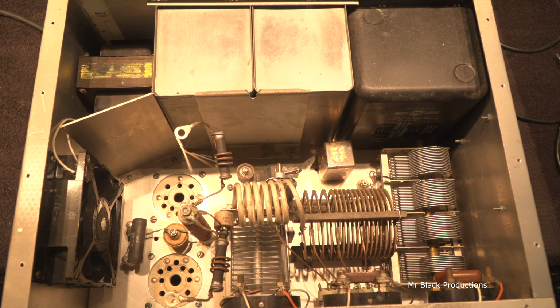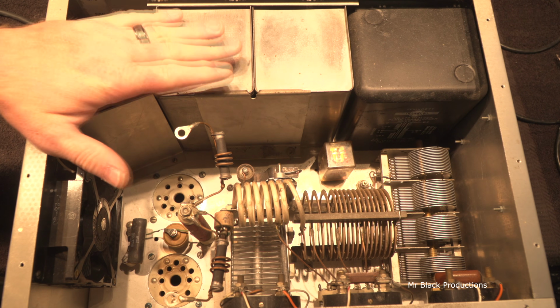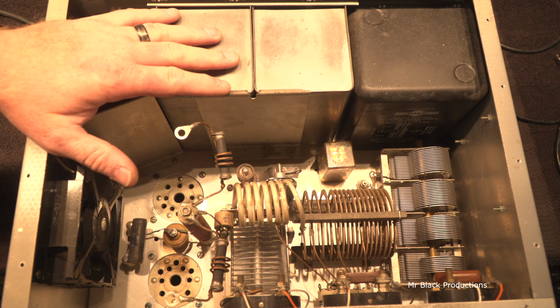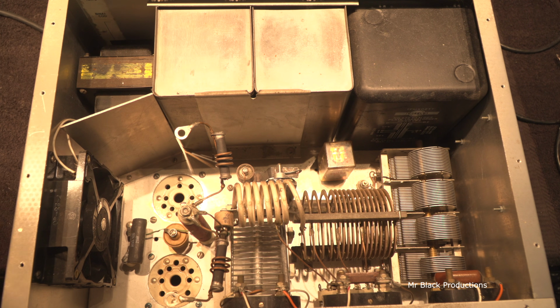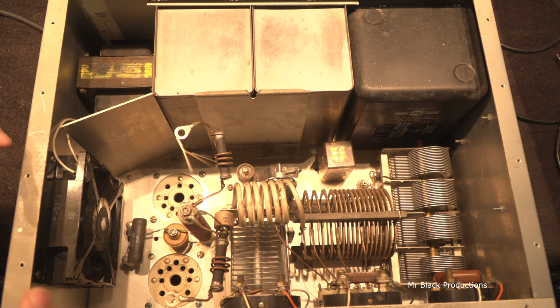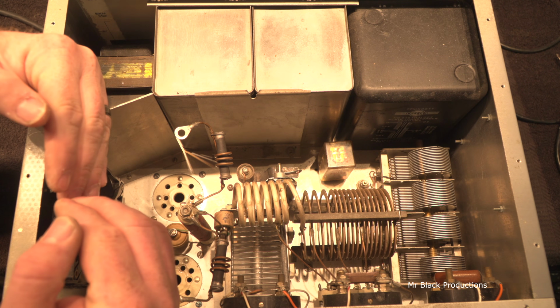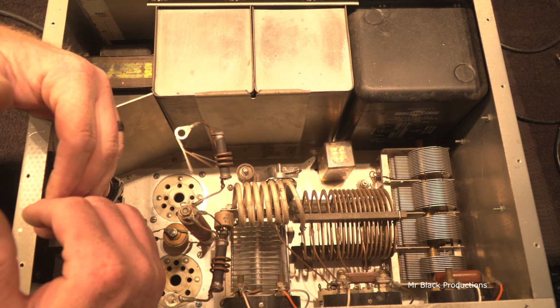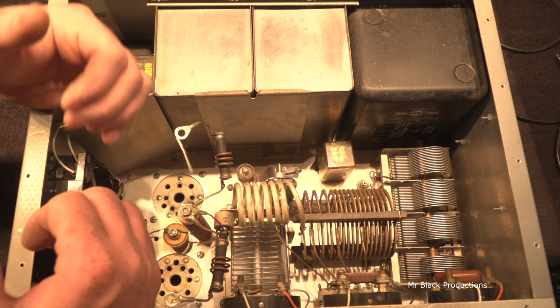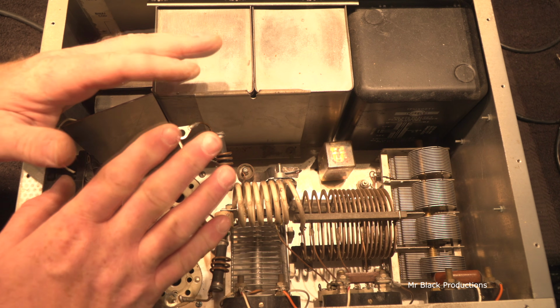Shipping is such a violent process, especially with something very heavy like this. We have to check if the cabinet's bent internally, if the floor is bent. If the floor is bent, is it putting undue pressure on one of the tuners? It might cause the tuner to bend, cause the fins to arc, meaning they're touching. Just slow down and look.